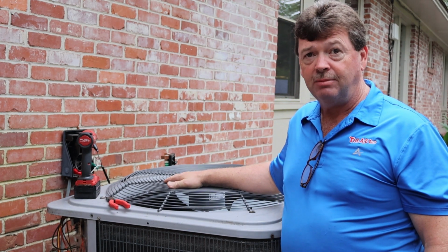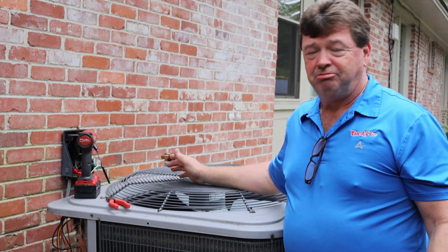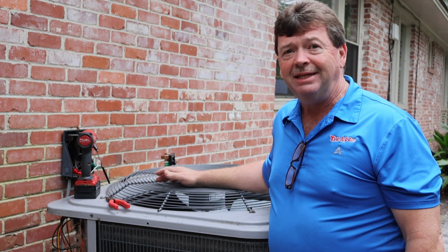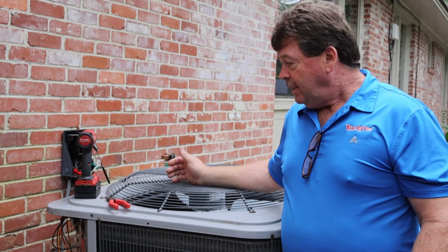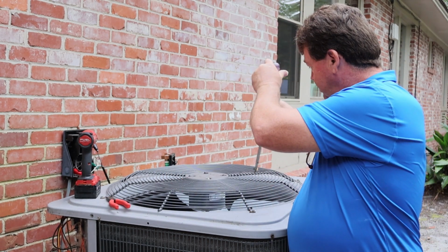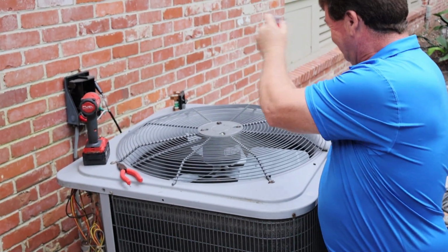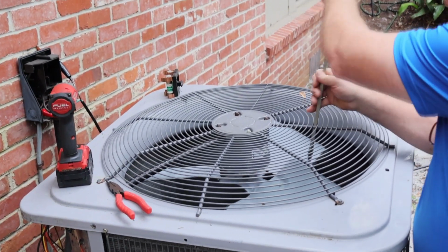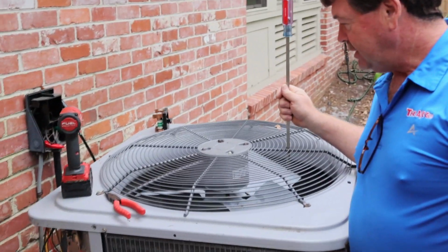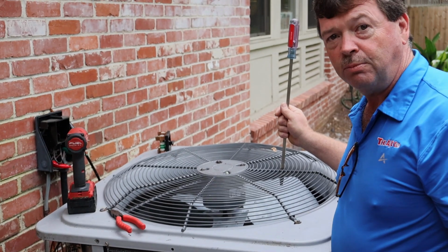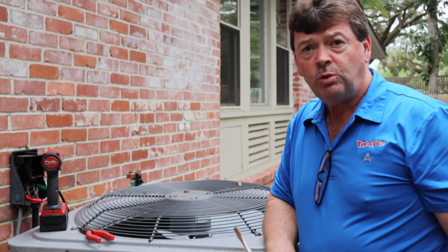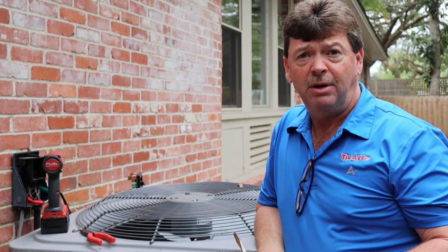We'll eventually take the top off so we can get in there and clean the leaves out of the bottom of the condensing unit. What I always like to do, something that gives me some insight on the condition of the condenser fan motor, is generally take a screwdriver or something and just spin the blade, like so. You can see how it spins easily and continues to spin, so the bearings are probably not dry in this motor. It's probably fine, and we'll check the bearings when we get the top off so we can get to the shaft of the motor. But that tells me that the bearings are not dry.